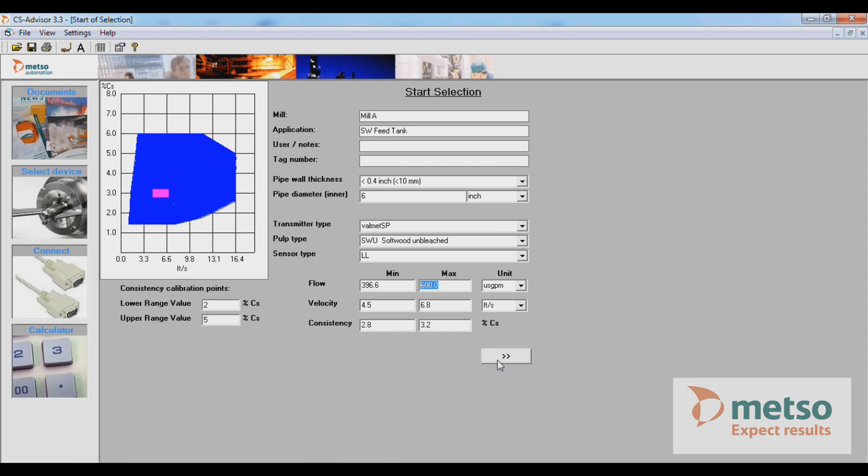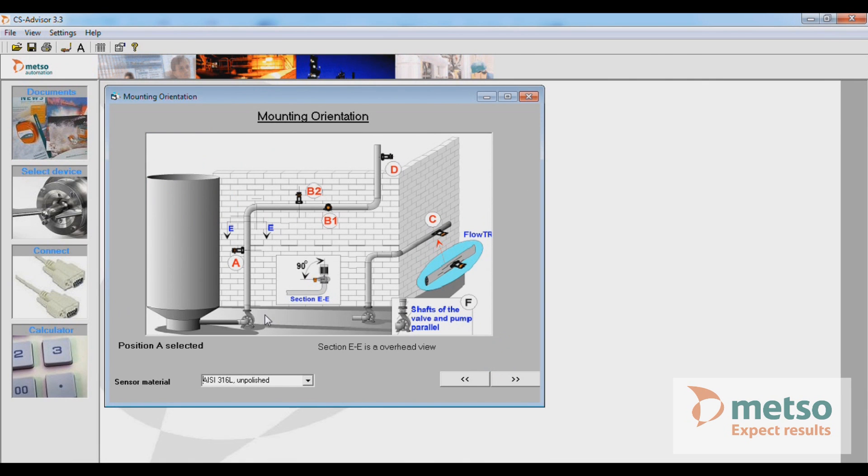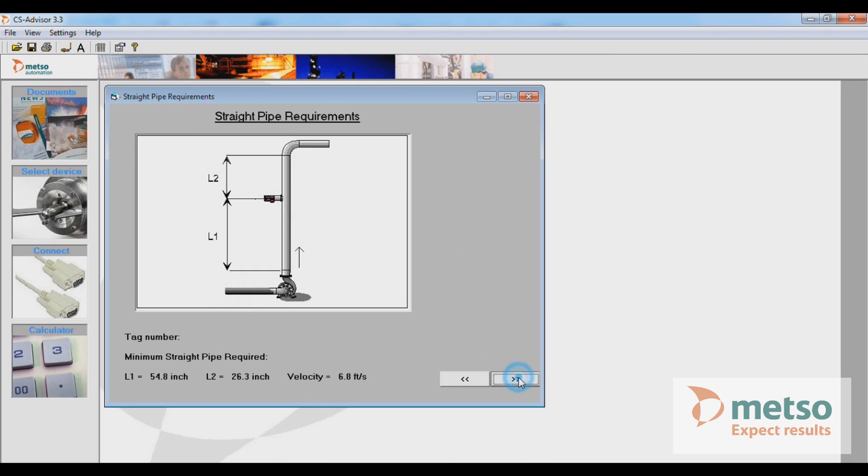So we're going to go to the next step. In our scenario, we're going to have a vertical up installation. We're going to select that, go to the next screen. It automatically calculates our L1, our straight pipe requirements before the SmartPulp, and our L2 straight pipe requirements after the SmartPulp.